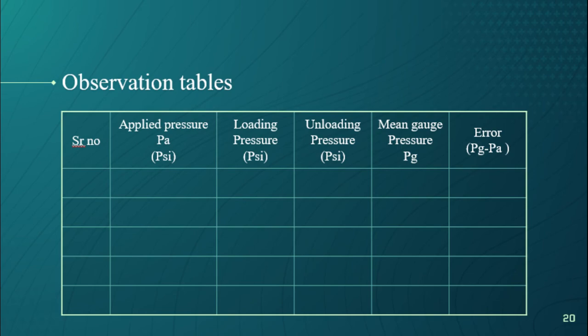Similarly, we will note down the reading for unloading case from the gauge. In the mean column, you will take the mean of loading and unloading pressure across every applied pressure. To find out error, we will subtract the applied pressure value from the mean value. In this way we will be able to calculate error of Bourdon gauge in every reading.